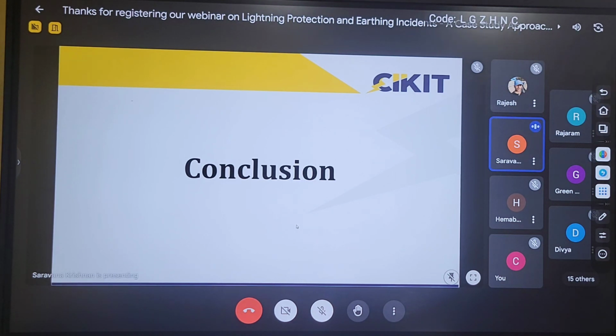And most importantly, in earthing, if I want to change the material from copper to GA, I cannot match the cross-section area alone. So I have to perform the current carrying capacity calculation. If I want to change the material from copper to GA, I should not match the cross-section area. I have to check what will be the suitable size of GA that will be able to carry the same current as that of copper.